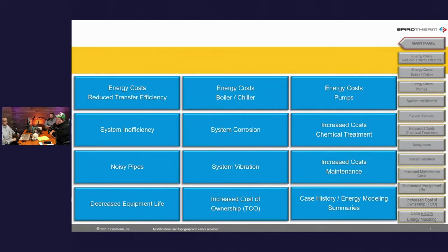Further with noise, we'll hear our pumps cavitating — you'll hear that vibration. We've heard what sounds like they're churning rocks in there. That's actually air bubbles expanding about 1,000 times from the differential pressure. It's very damaging — you can really eat up an impeller quickly with cavitation. It also damages pump seals. So air can actually shorten the life of pumps. There are a number of reasons why we care about air.